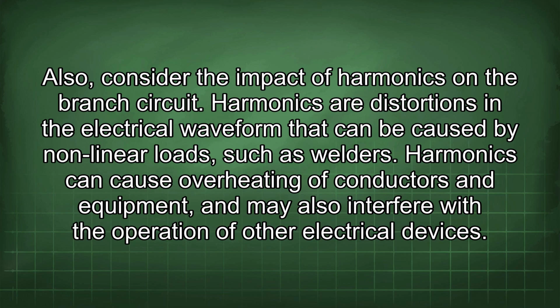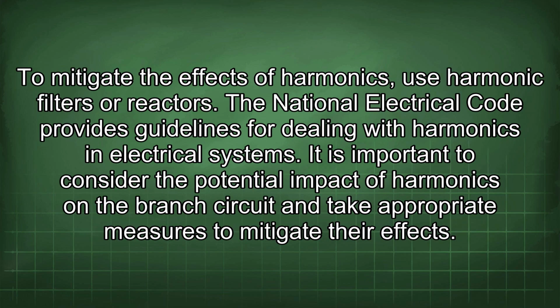Also, consider the impact of harmonics on the branch circuit. Harmonics are distortions in the electrical waveform that can be caused by nonlinear loads, such as welders. Harmonics can cause overheating of conductors and equipment, and may also interfere with the operation of other electrical devices. To mitigate the effects of harmonics, use harmonic filters or reactors. The National Electrical Code provides guidelines for dealing with harmonics in electrical systems. It is important to consider the potential impact of harmonics on the branch circuit and take appropriate measures to mitigate their effects.